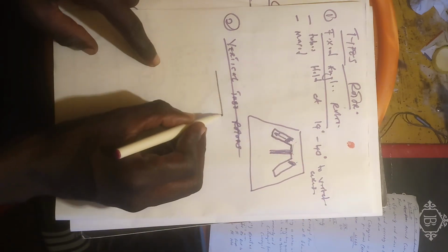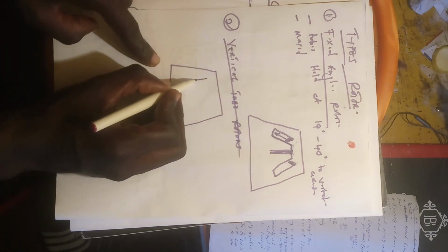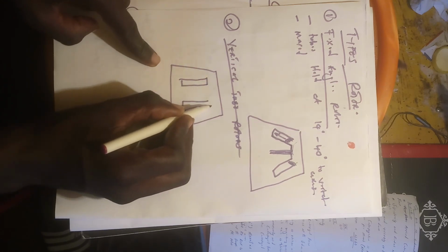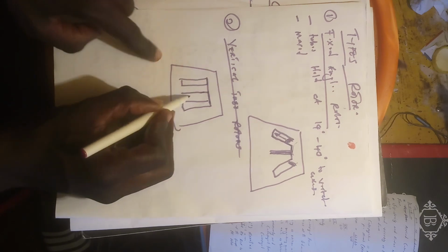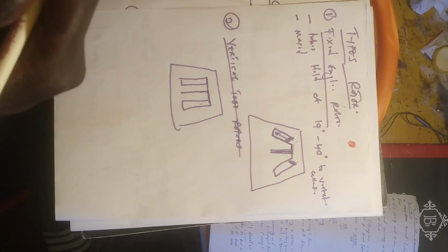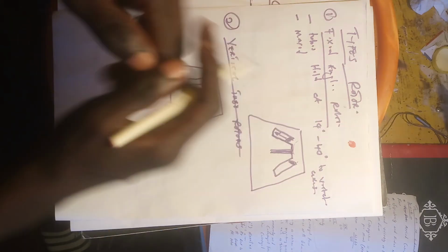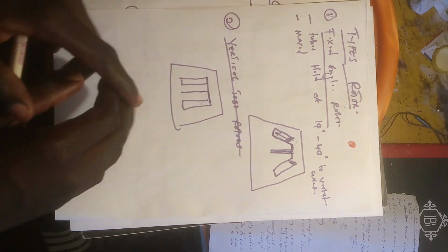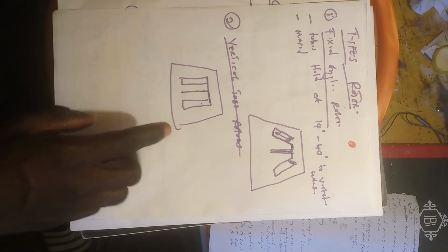How these vertical tube rotors look is like this. You have this being the axis and holding the tubes just vertically parallel to the rotor axis.